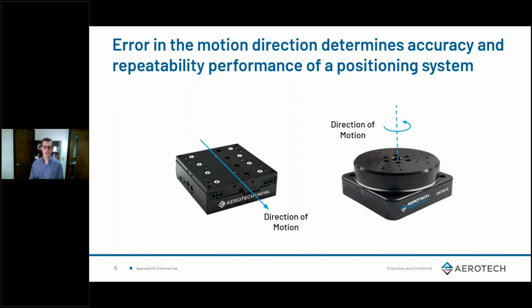In the direction of motion, a motion supplier would typically refer to an accuracy and a repeatability, just as we talked about. In our case, for a linear stage we would use a laser interferometer with an optic at the work point to measure the accuracy and repeatability along the direction of travel. For a rotary stage, we would use an autocollimator and a master axis to measure in the direction of travel. Essentially, we're doing just as we did with the dartboard. We're measuring the commanded position to the stage in the software, and then the physical actual position as measured by the external device.